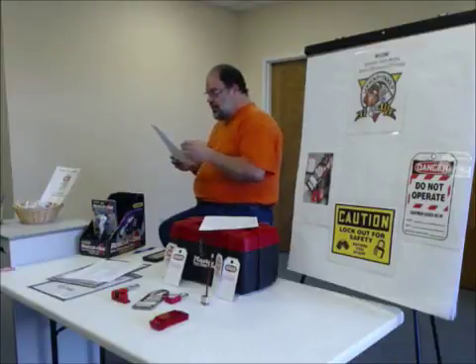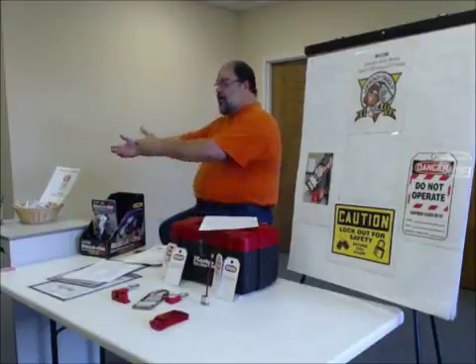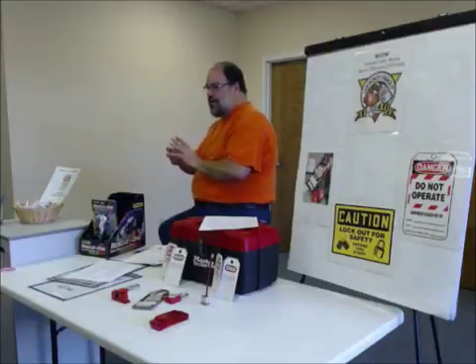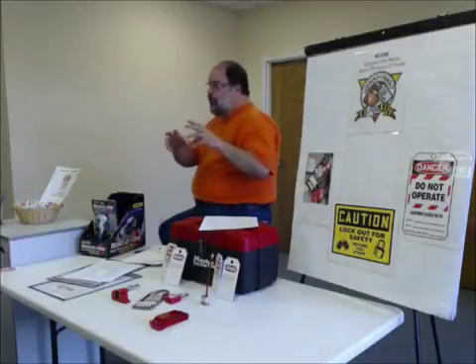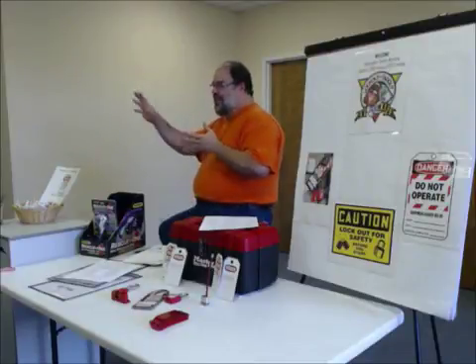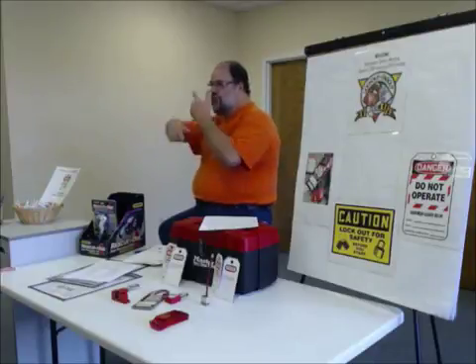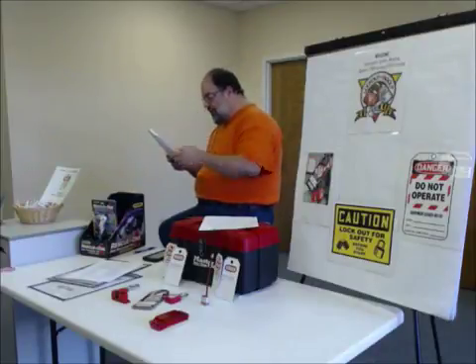Once you've locked out each of those, disconnected them and locked them out, then you're going to phase out. For example, if you've got an airline coming to a piece of equipment, I unhook the airline and I lock that airline out. Have I eliminated all dangers associated with pressurized air? No. Why? Because there could be, and probably will be, a storage of air built up in that piece of equipment. So we've got to bleed, or in this case, phase out that existing stored energy. It's only potential, but because it's stored in the equipment, it could fire off. It could cause it to cycle. So we need to bleed off any energy that's stored up in the machine. And that's called phasing out.